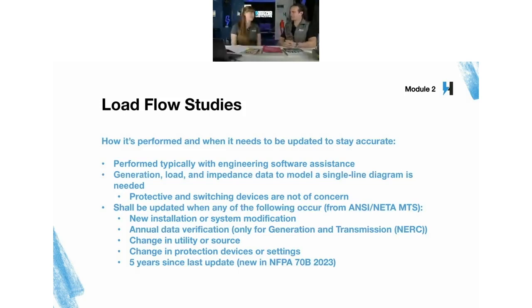What do you do to perform it? Again, you need a single line diagram, and it's typically performed in engineering software, because nobody's really doing these by hand anymore. It takes too long and is too expensive. First, you'll need input data for the study: generation or generator information, load information, and impedance data to model the single line diagram. All this information will be used in the study, but protective devices and switching devices aren't used in the study. That's a basic explanation of load flow studies.